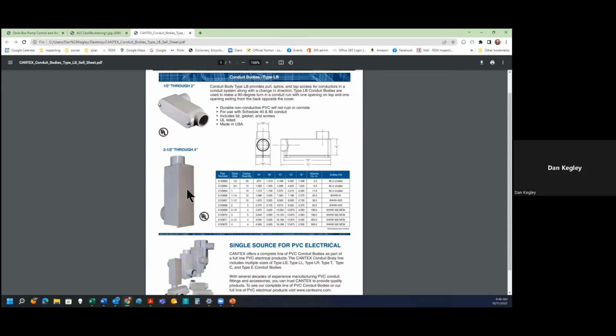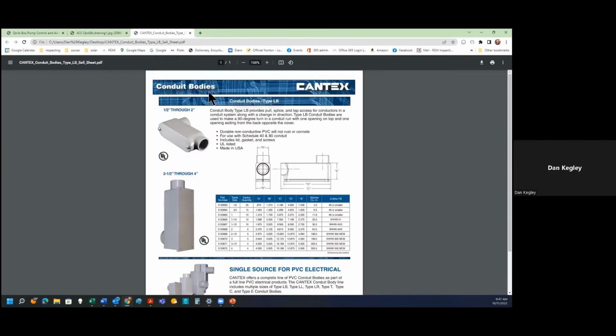And then there is sufficient space in here too to actually have wire nuts and those kinds of things. So they're allowed to be a splice where if you want to have two wires and splice them together inside there, you can certainly do that, but they're not big enough to house a receptacle and those kinds of things in addition to the other stuff. But these are conduit bodies as listed in the code, but they're not considered junction boxes. Good to know.